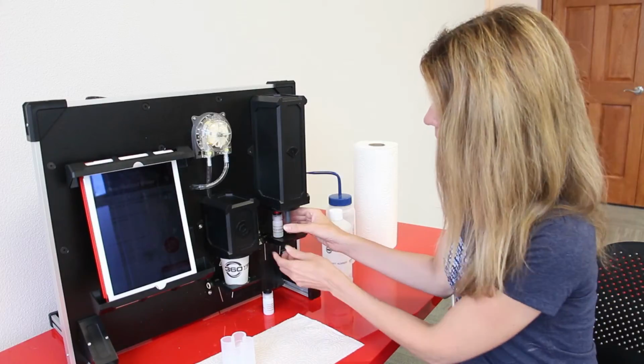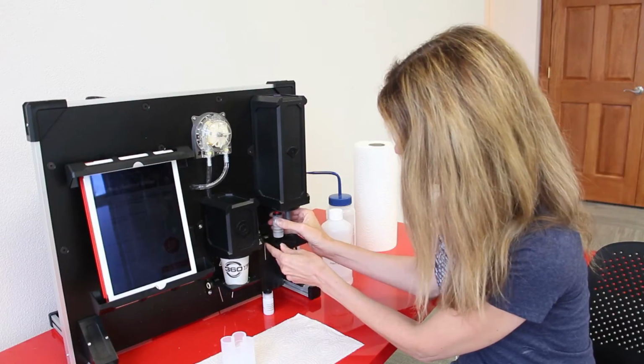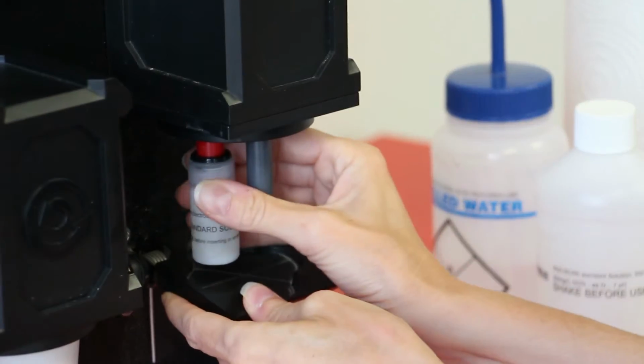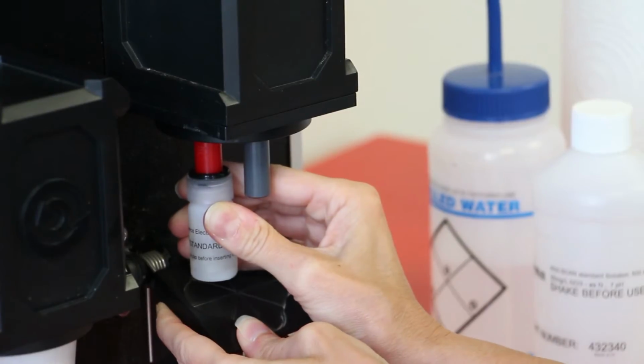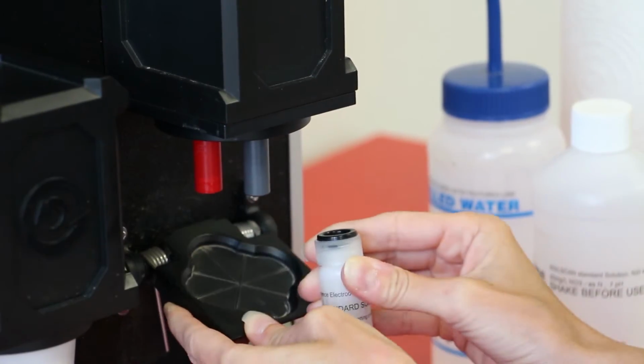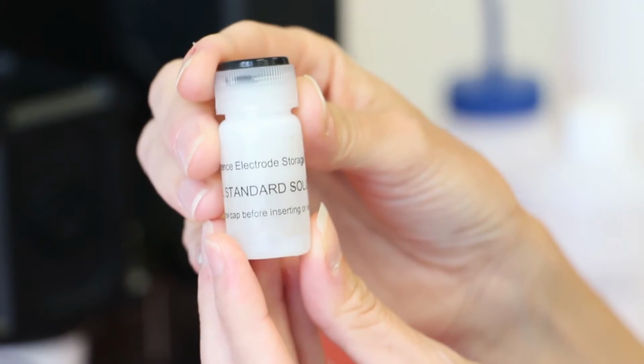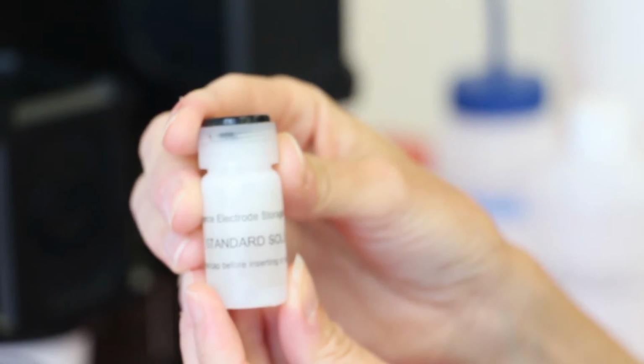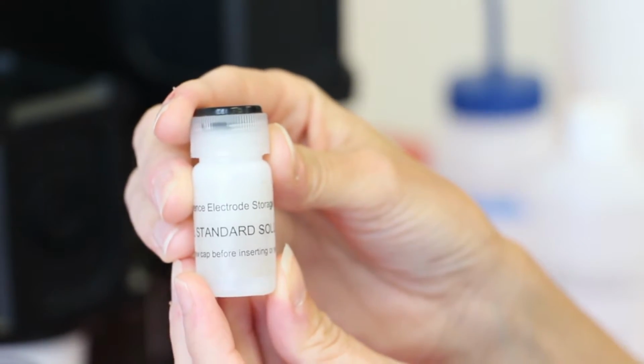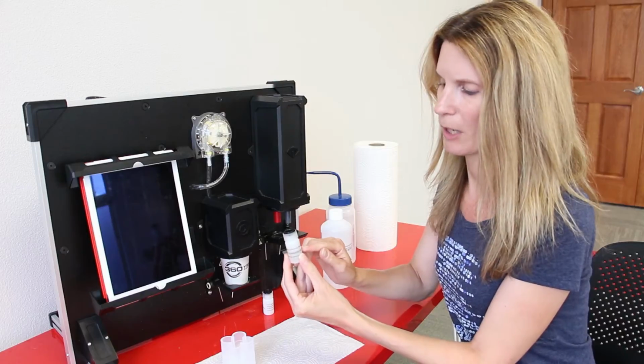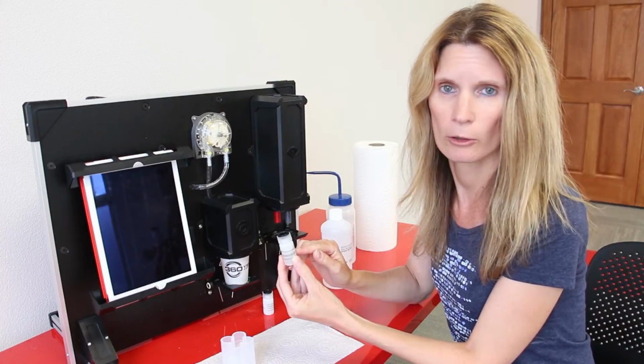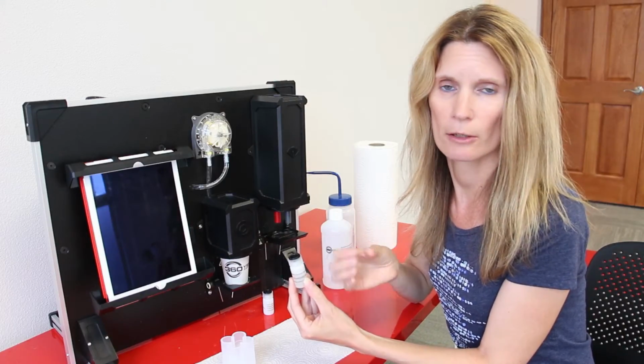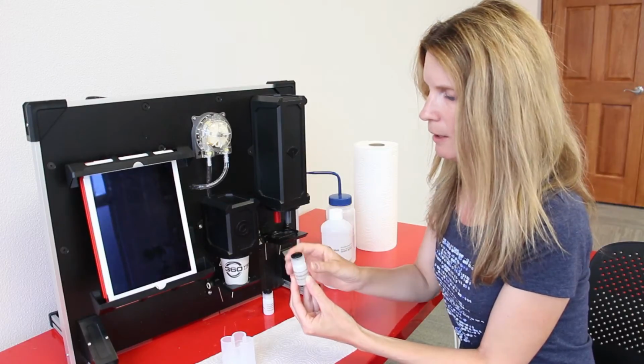Now that's a little bit different on the red sensor here. The red sensors are reference electrode. And we're going to pull this one off. This one comes off just a little bit hard. And this one's identified as the reference electrode storage bottle. It has an indication on there that you fill it with standard solution. If you fill it about 3/4 or half the way full and let it soak in there, you should be good to go on that for storage.